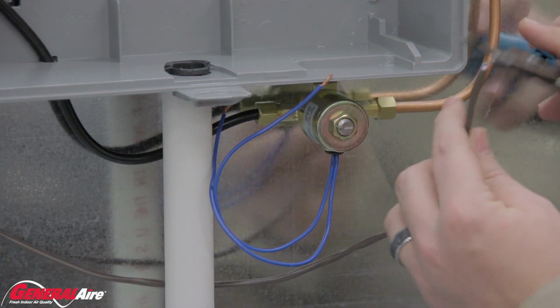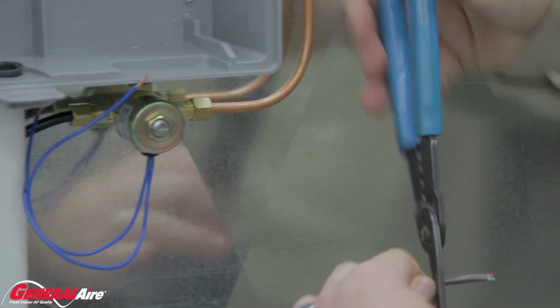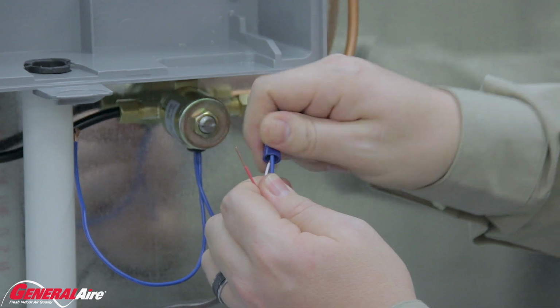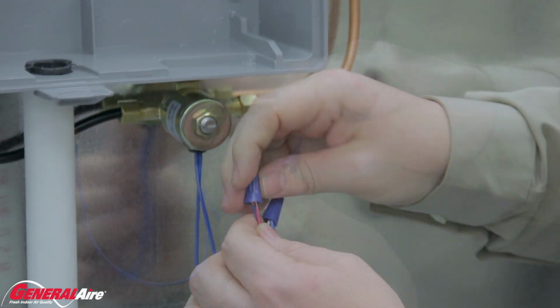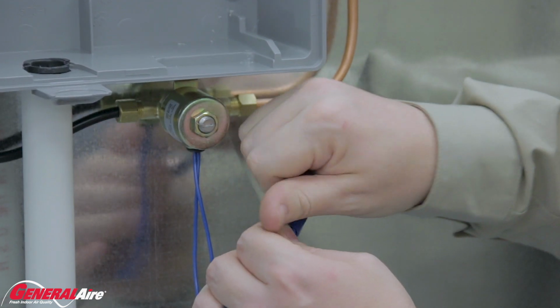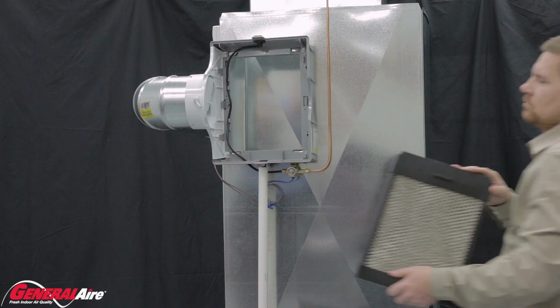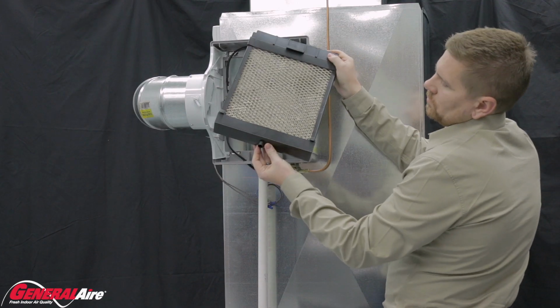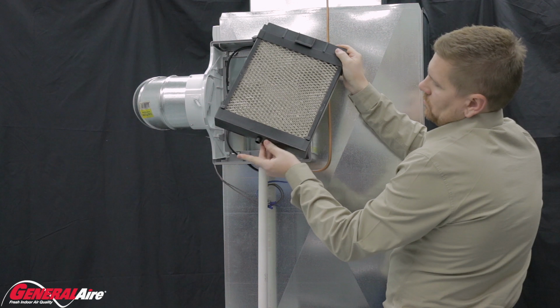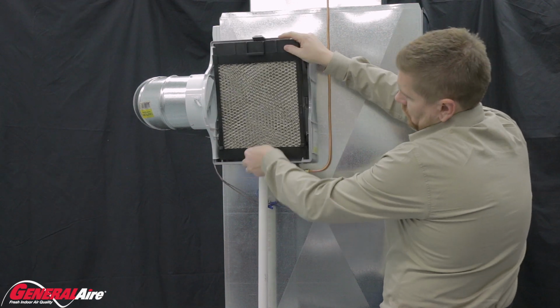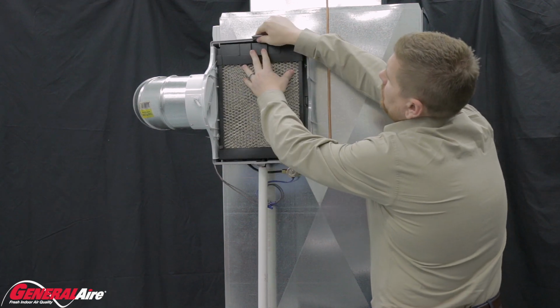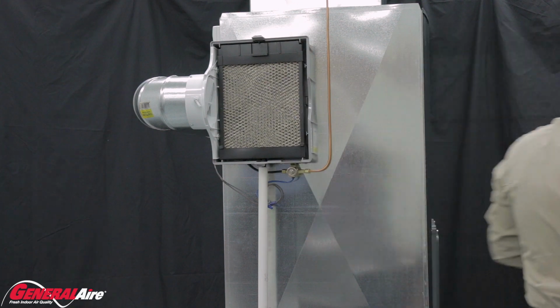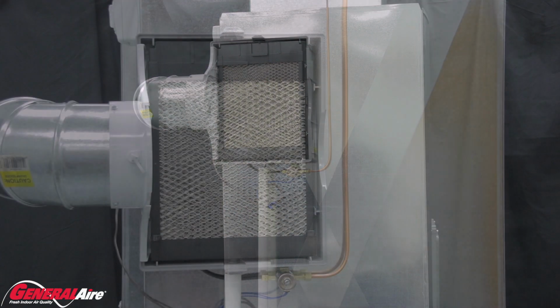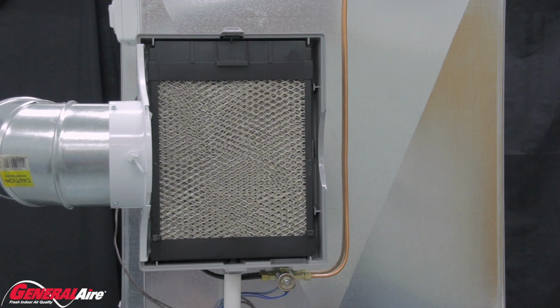Now run the wiring to the solenoid valve. Use your wire strippers to strip the wire. Use wire nuts to connect the wires to the solenoid, ensuring a snug connection. Next, you will insert your vapor pad housing into the chassis. The drain on the drain pan should fit into the drain of the chassis base. Push the vapor pad into the chassis frame, making sure the pad assembly is secured by clicking the assembly into the top of the frame.